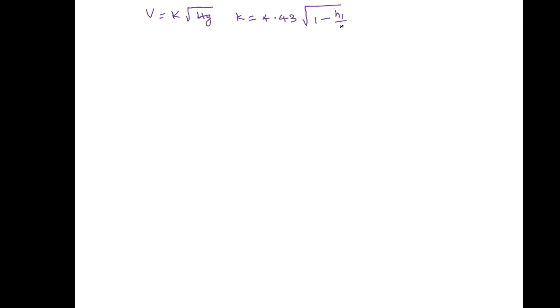Now this velocity V is equal to K square root of Hg, where the K value was given as 4.43 square root of 1 minus H1 divided by Hg. But this K value is different for different materials. Generally we take K as a constant: 0.825 for a brick chimney, and K is equal to 1.1 for a steel chimney. K value is going to vary.